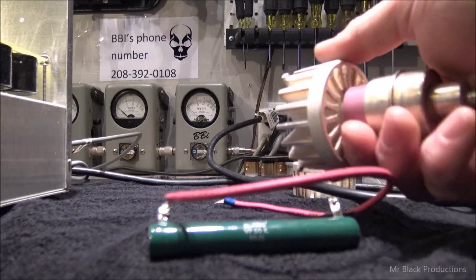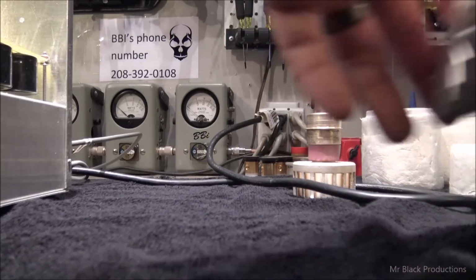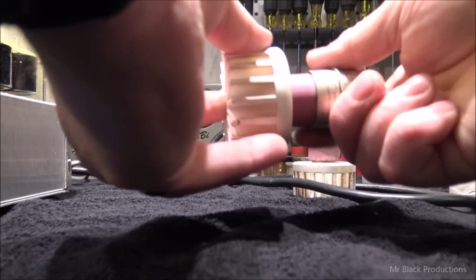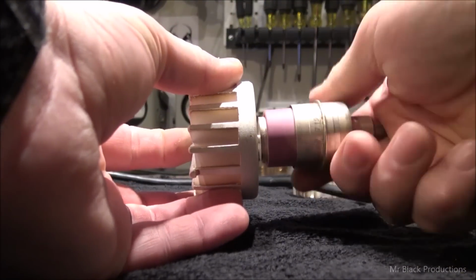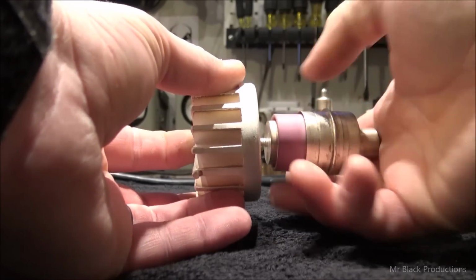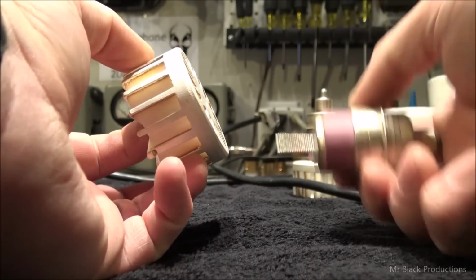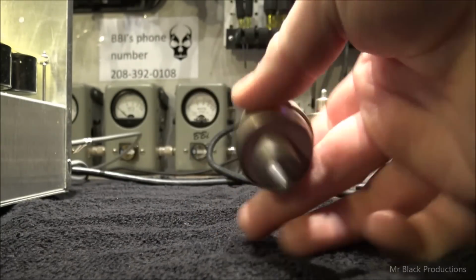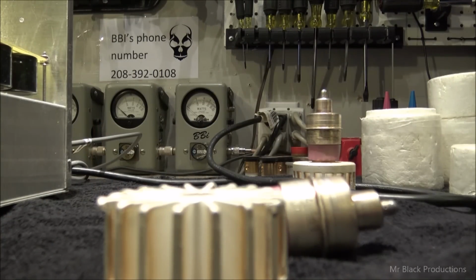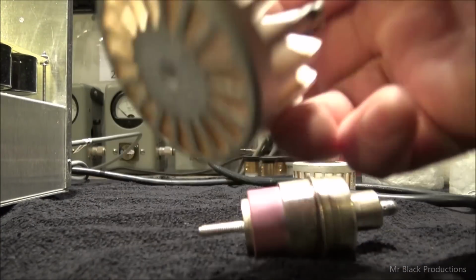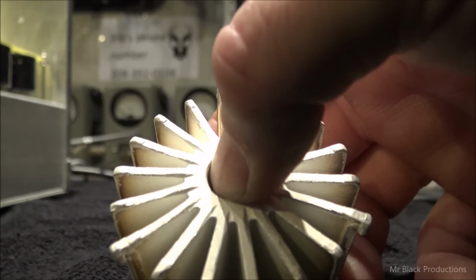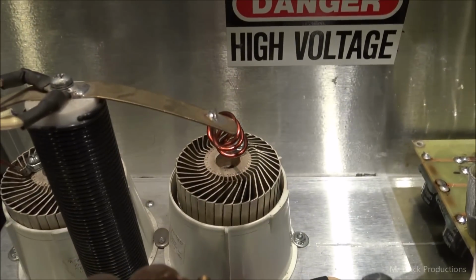I took the anode head off. As you guys can see, the anode head unthreads from the tube body. That's the actual tube itself, and that's the anode, or the heat dissipation portion of it, the head. The reason I went to the other heads is that these don't have holes in them for mounting the high voltage, like what's right down in there.